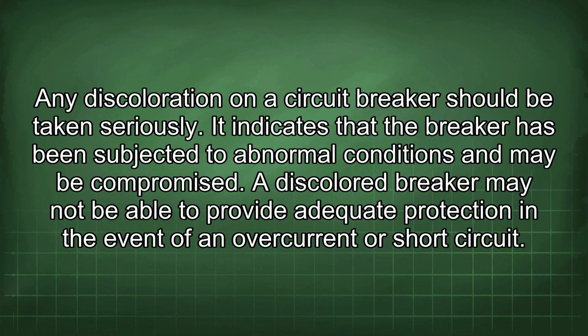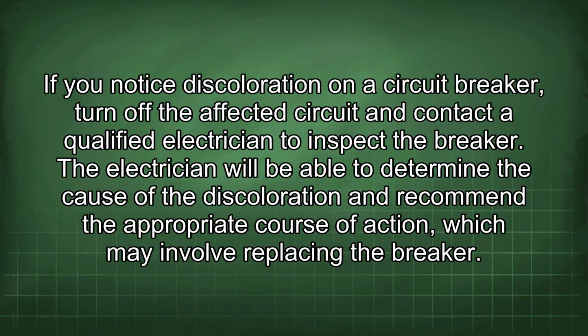Any discoloration on a circuit breaker should be taken seriously. It indicates that the breaker has been subjected to abnormal conditions and may be compromised. A discolored breaker may not be able to provide adequate protection in the event of an overcurrent or short circuit. If you notice discoloration on a circuit breaker, turn off the affected circuit and contact a qualified electrician to inspect the breaker. The electrician will be able to determine the cause of the discoloration and recommend the appropriate course of action, which may involve replacing the breaker.